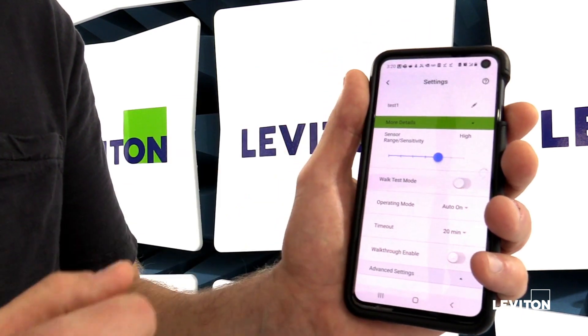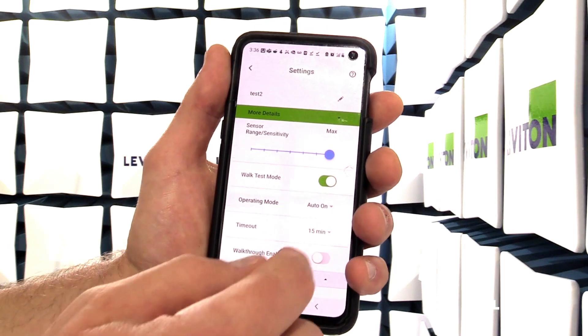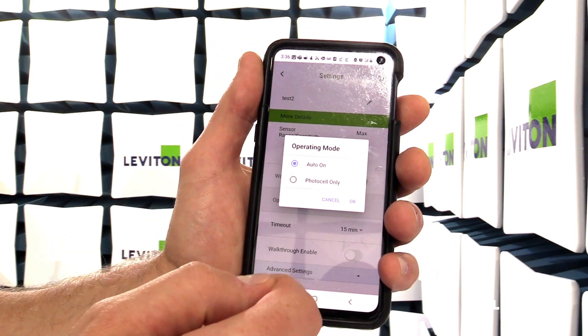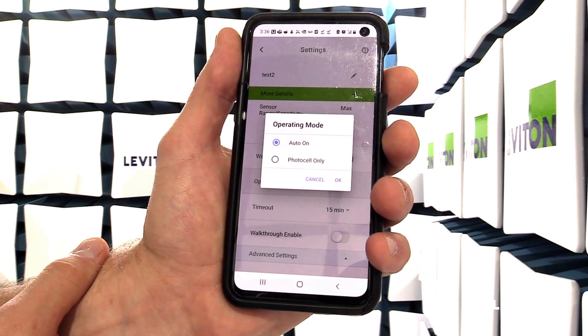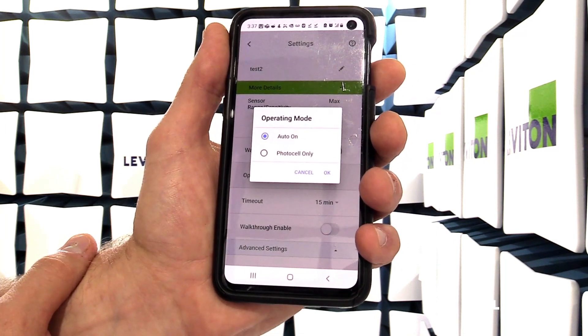You can now see that it shows up as test two on the app. For operating mode there are two options: auto on or photocell only. In photocell only, it will disable the occupancy sensor and operate only based on the ambient light available. There are several photocell operating modes which we will walk through later.